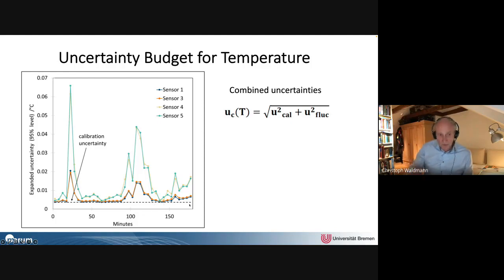And there's another aspect I mentioned already, this calibration uncertainty. This dashed line sets a lower limit, so you cannot go beyond less than that. And this is about 3 millikelvin. Some people are claiming they can do better than 1 millikelvin. Again, the temperature scale is not defined to that degree. So the stability can be like that, but not the accuracy or uncertainty in that case. So it's up for discussion. Maybe if you have different views on that, let's discuss it later.